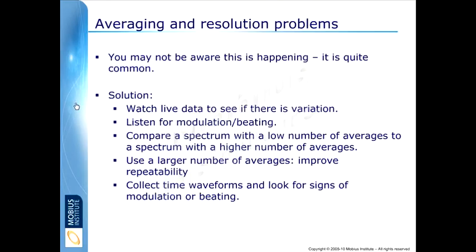If you look at live data, sit there with your analyzer and just, if you've got the option, watch the data live. As I mentioned, listen for the modulation and the beating. Compare two spectra. Just sit there with four averages and take one measurement, take another one, take another one and see if there's variation between them. Use a larger number of averages.